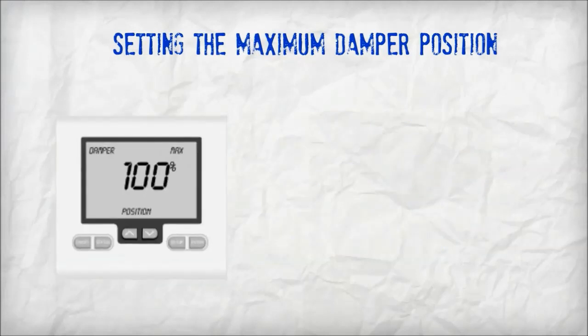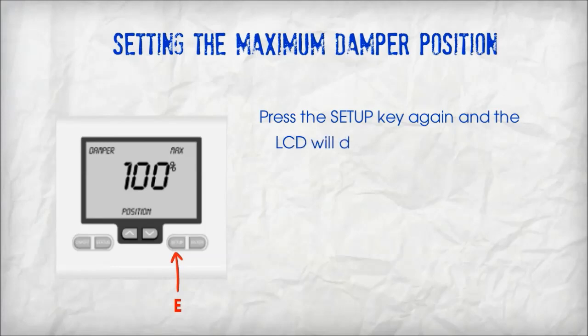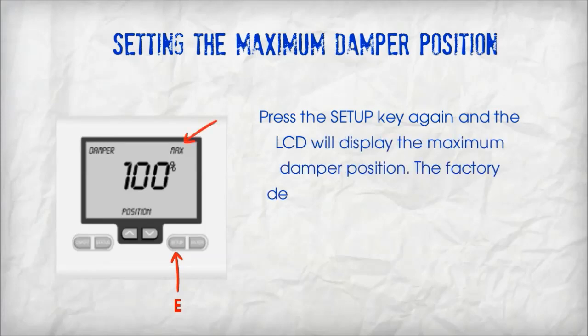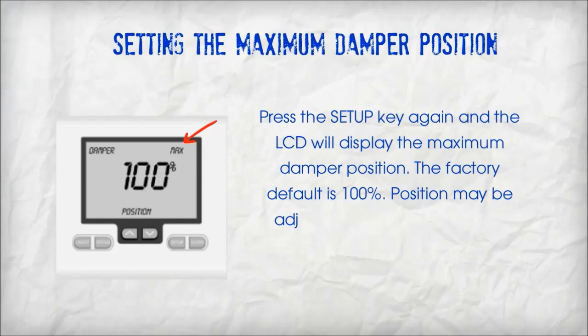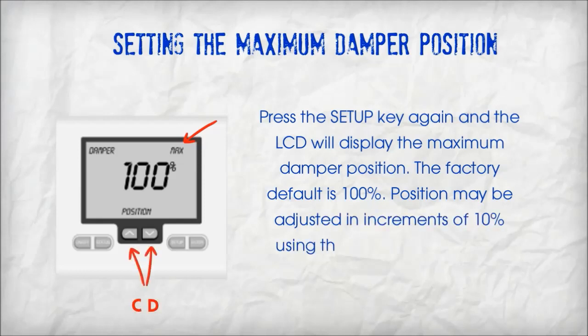Setting the maximum damper position. Press the setup key again and the LCD will display the maximum damper position. The factory default is 100%. Position may be adjusted in increments of 10% using the up and down keys.